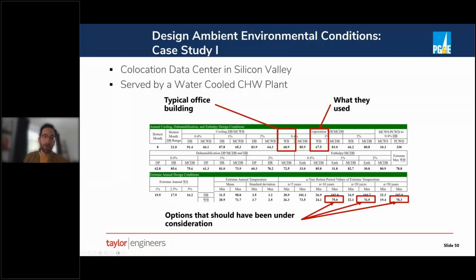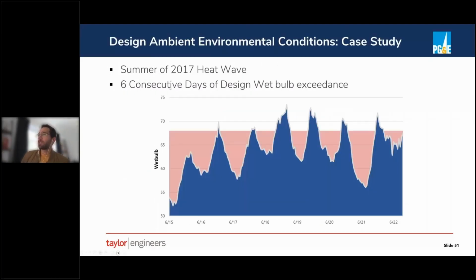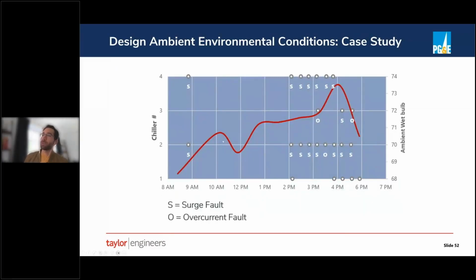So what was the ultimate impact of this error on the part of the engineer? Well, during the summer of 2017, we had an extended heat wave that was not only warm, but it was also humid. So there were 6 consecutive days where the ambient wet bulb exceeded the design condition for this data center. And the worst of those days you can see was 6/18, which I think was a Saturday. And that weekend we got a call from the owner, hey, we've been having issues with our chilled water plant with chillers tripping all weekend. What can you do to help us?